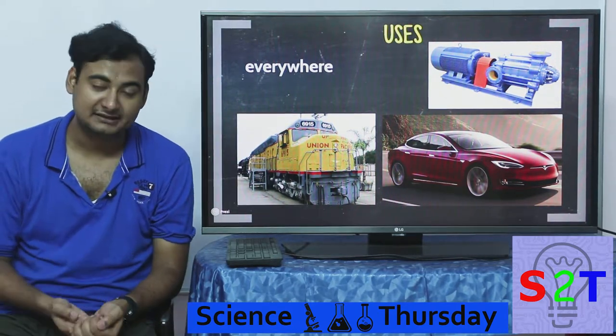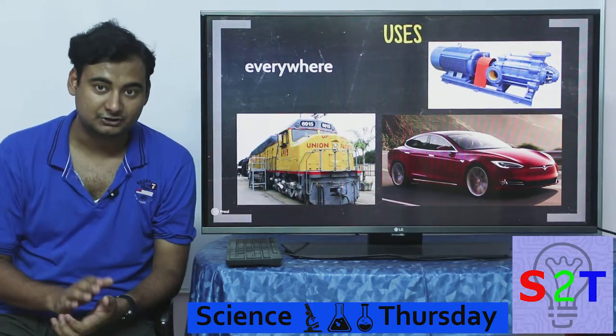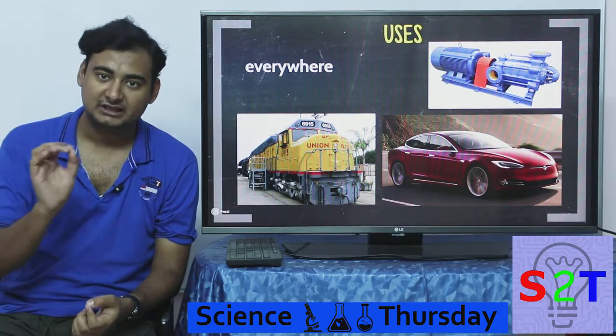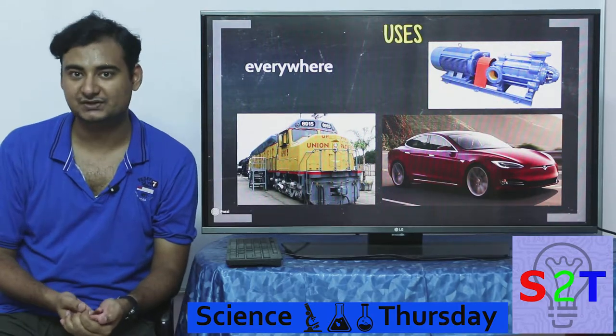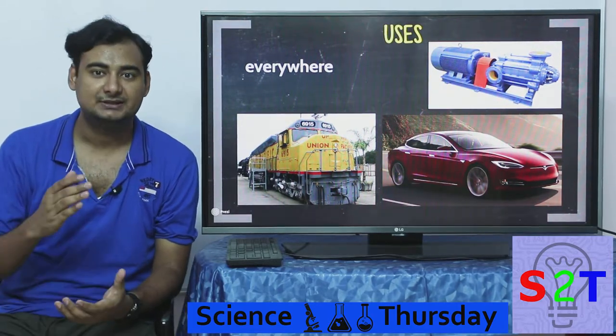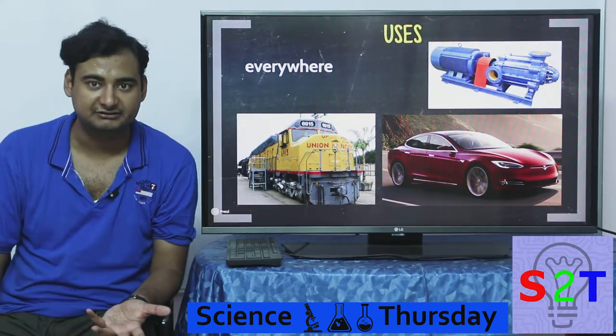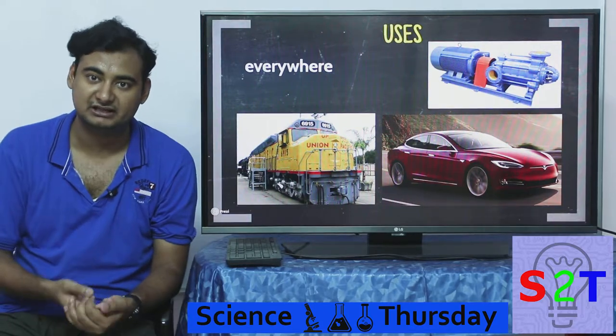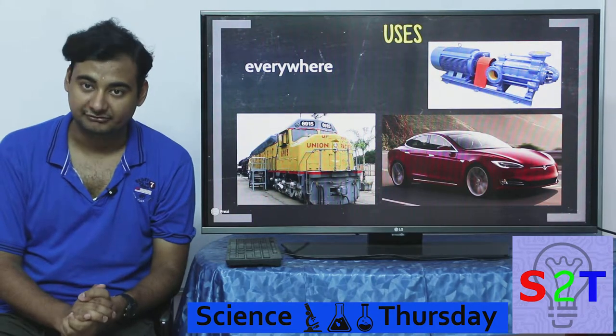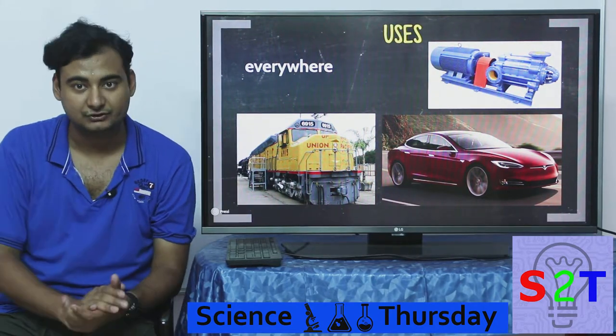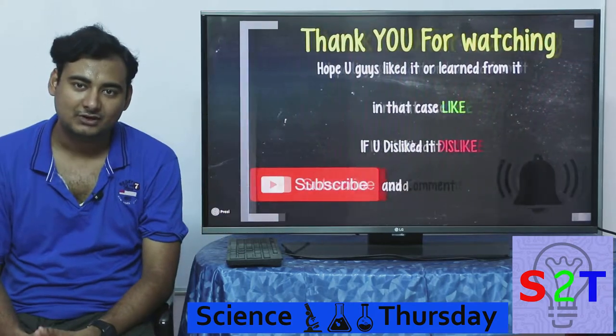Due to the relative simplicity of induction motors and our advancements in inverter technology, we can now control them in very unique ways — controlling torque and RPM independently. This is the reason they are still widely used in industrial applications. For example, if you are using a grinding wheel, wood and metal require different grinding speeds. We employ a variable frequency drive, where you can change the frequency and the motor simply adapts to it.